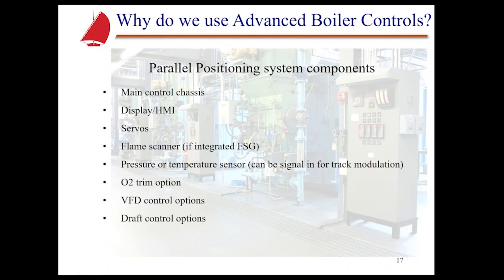Now, another selection you're going to make, and most are getting this anymore, is going to be O2 trim. At that point, you'll decide whether or not you need O2 trim, and you'll buy the components necessary for that. That's going to be a sensor that's installed in the stack. A variable speed drive. If you're going to use a variable speed drive for the combustion air, which most are doing now because the reliability has gotten better, the costs have come down to a certain extent, and they just save a ton of power. That's all there is to it. So you're going to need to select that VFD based off of the motor size, obviously, on that particular burner.